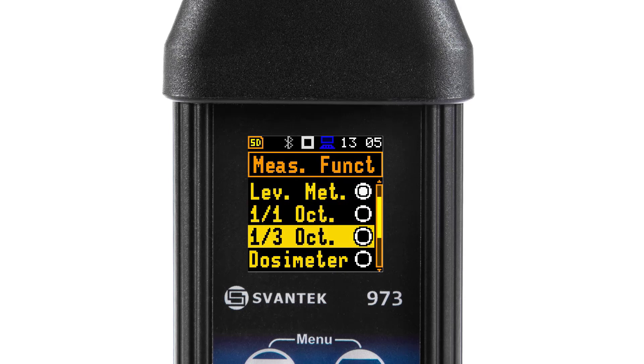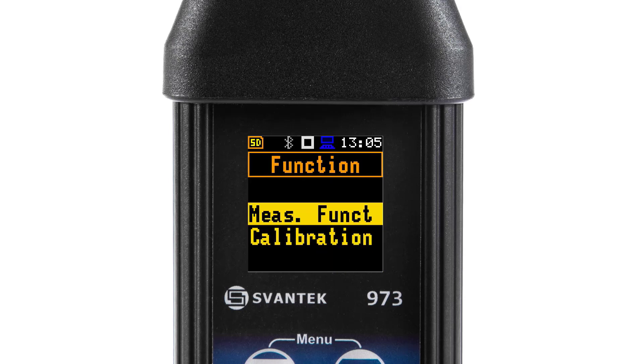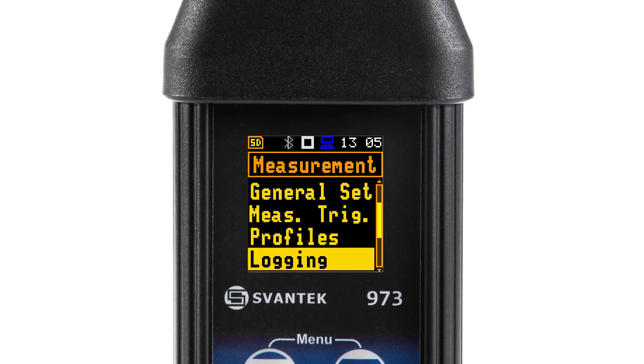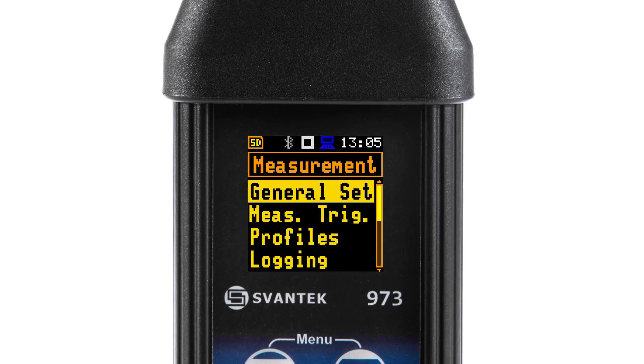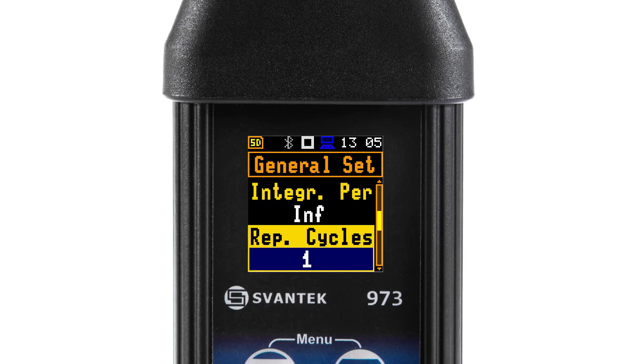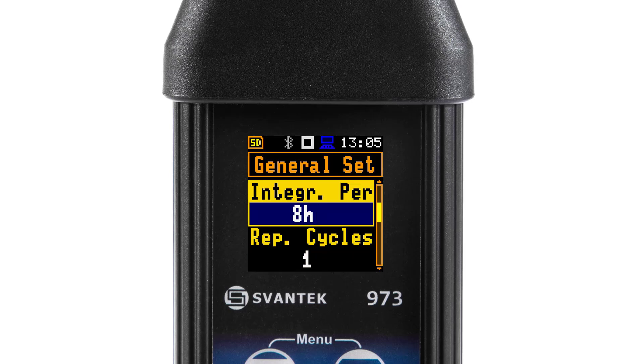Execution of the 1/1 octave or 1/3 octave analysis depends on certain sets of parameters configured in the measurement section. The averaging of results for each spectrum band is performed during the integration period and is repeated the repetition cycle number of times. Both parameters are defined in the general settings list.